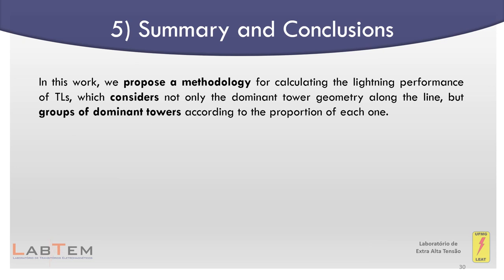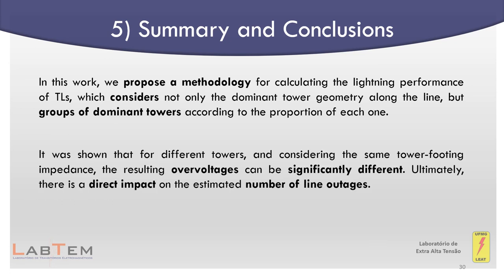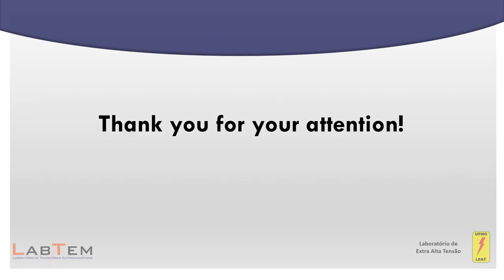In this work, we propose a methodology for calculating the lightning performance of transmission lines which considers not only the dominant tower geometry along the line, but groups of dominant towers according to the proportion of each one. It is shown that for different towers considering the same tower foot impedance, the resulting overvoltage can be significantly different. This difference directly impacts the determination of critical current and the probability of it being exceeded, ultimately leading to a direct impact on the estimated number of line outages. Thank you for your attention.